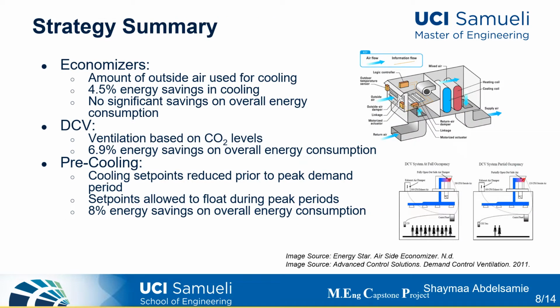Our next step was to apply energy conservation measures, ECMs. Our first ECM was deploying economizers. When outdoor temperatures are low enough to cool the building, outdoor air is drawn into the building using economizers. This strategy resulted in a 4.5% reduction in cooling loads. However, it did not show significant reduction in total energy consumption. Our second strategy was demand control ventilation. This strategy resulted in a 6.9% reduction in overall energy consumption. Our final strategy was pre-cooling. We reduced the cooling set point 4 hours before the peak demand period and allowed the set point to float during the peak demand period. This strategy resulted in an 8% reduction in overall building energy consumption.